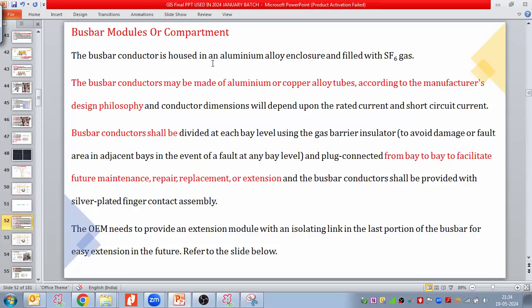So the bus bar conductor is housed in an aluminum alloy enclosure filled with SF6 gas. As we have already discussed, the bus bar conductors may be made of aluminum, or made of copper alloy tubes, according to the manufacturer's design philosophy. It totally depends on the manufacturer's design philosophy and the conductor dimension. It will also depend upon the rated current of the common bus bar and the rated short circuit current of the bus bar. So taking these parameters, the manufacturer will decide the dimension, the size of the bus bar conductor.